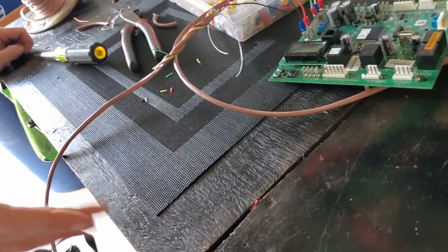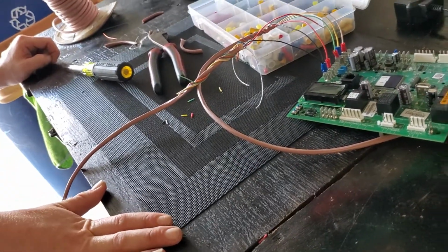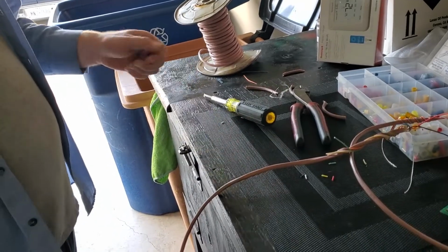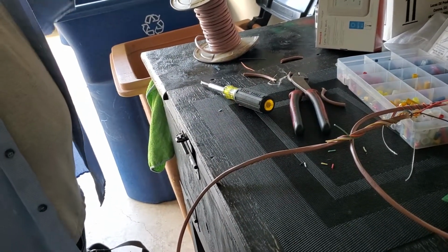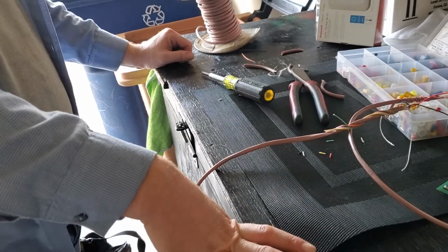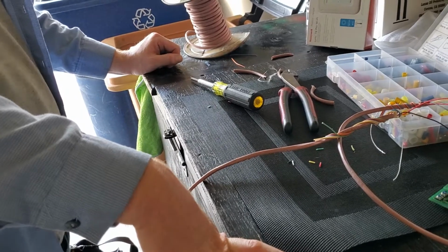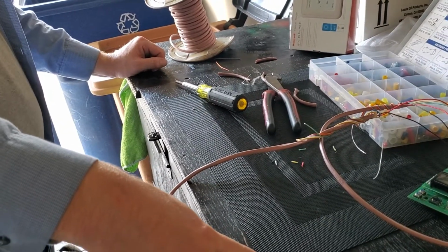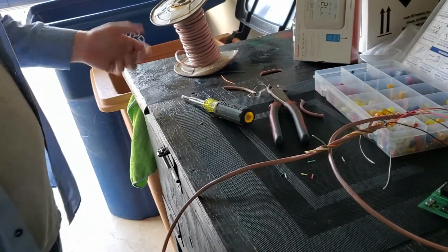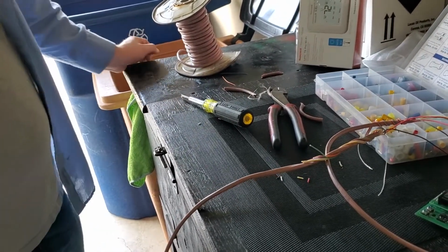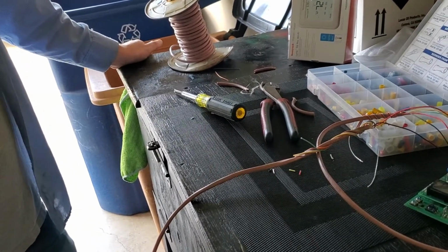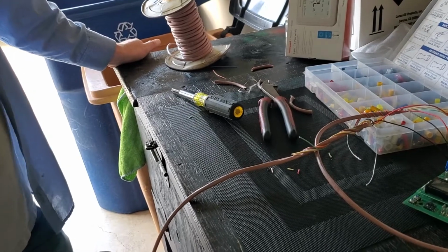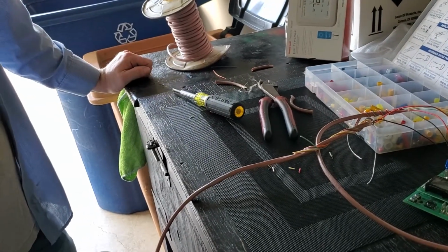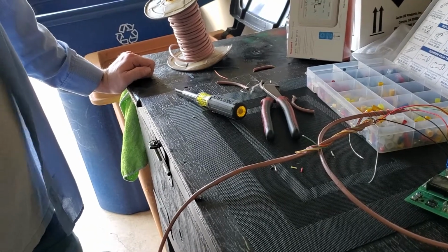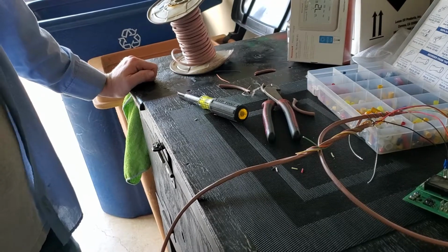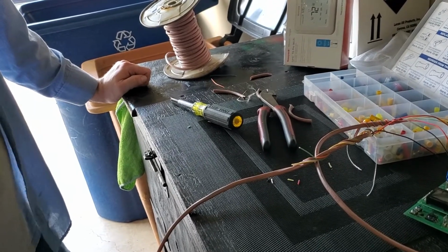Dude, do you want to know something funny? I went on a service call this morning. We had some guys out doing maintenance yesterday, just changing filters, at a place with big package units. Guy calls in and says, y'all were just out here doing maintenance yesterday, and now my RTU number 7 isn't working, and it serves the big boss's office. So I go out there, found a tripped breaker, turned it off, went up to the unit and started checking it out. First thing I did was ohm out the compressor to ground, and I've got a compressor shorted to ground, tripping the breaker. He goes, so it's just a coincidence that y'all were just out here yesterday doing maintenance and now this happens? I said, yeah, it is just a coincidence.